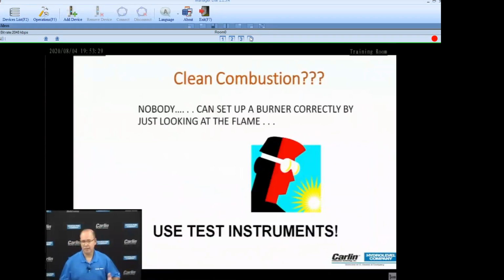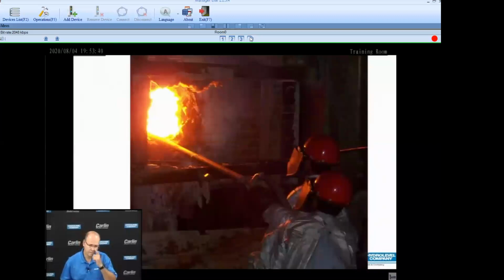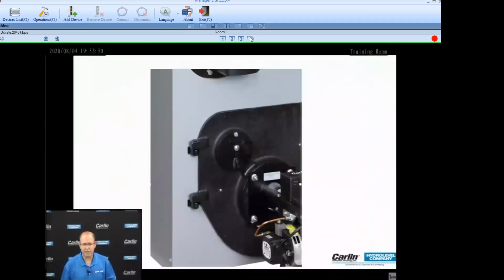So you got to use test instruments. Nobody can set up the burner correctly unless you got a pair of those glasses or you're using some test instruments. What are you looking at when you look at the fire? Okay, there's nothing to see there. I challenge technicians to adjust a burner without ever opening that peep door. When you're done, go ahead and take your smoke test, open the peep door, and take a quick look and see if everything looks fine. Guaranteed that if you got good results, it's going to look good when you look at that peep door.